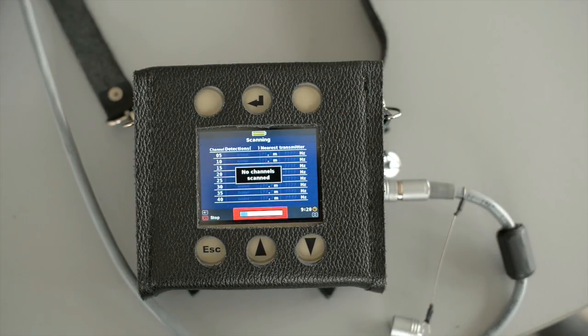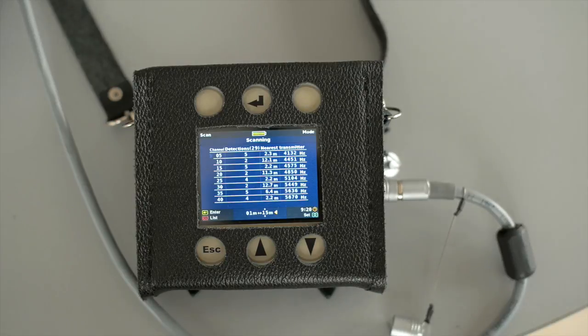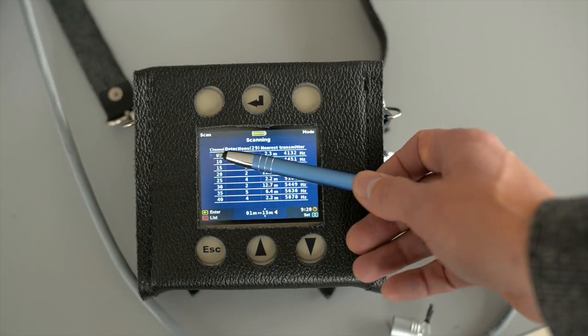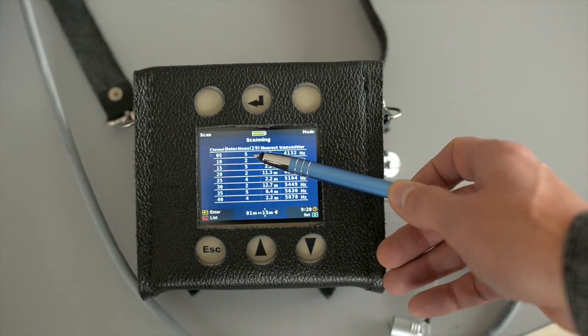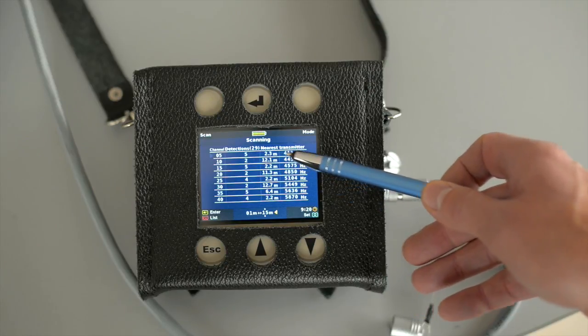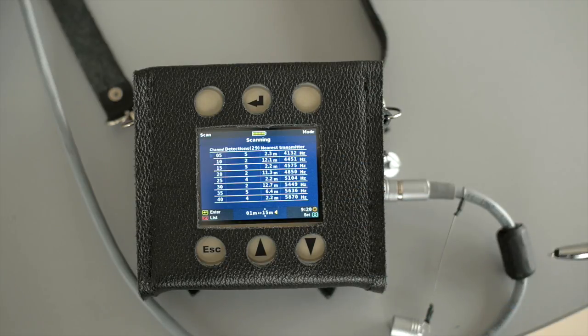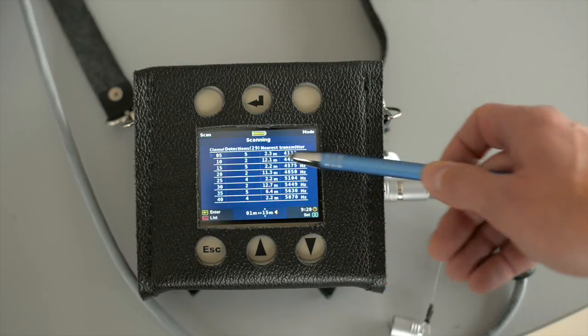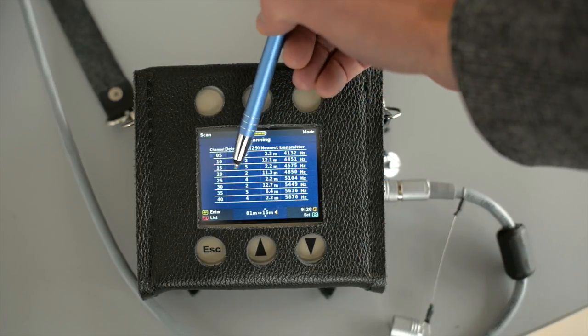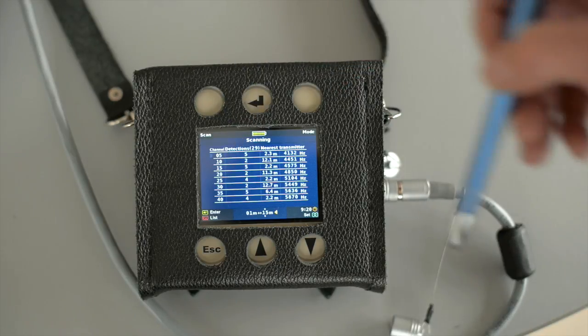The scan operation takes some time. The duration of this operation depends on the settings used in the Options menu. After the scanning process has been completed, the table will be filled in with the scan results. The table's columns will now display the following information: channel number, number of detected cap lamp transmitter signals, distance in meters to the closest transmitter, and its frequency in hertz.